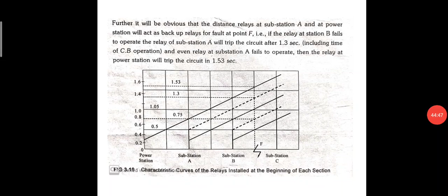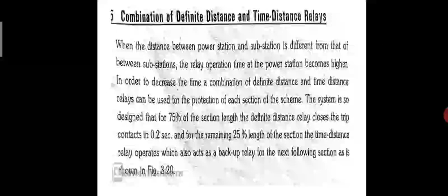And last one, combination of definite distance and time distance relays. When the distance between power station and substation is different from that between substations, the relay operation time at the power station becomes higher. In order to decrease the time, a combination of definite distance and time distance relays can be used for the protection of each section of the scheme. The system is so designed that for 75% of the section length the definite distance relay closes the trip contact in 0.2 seconds, and for the remaining 25% of the length of the section the time distance relay operates, which also acts as a backup relay for the next following section as shown in the diagram.